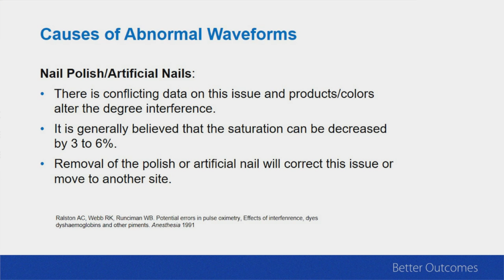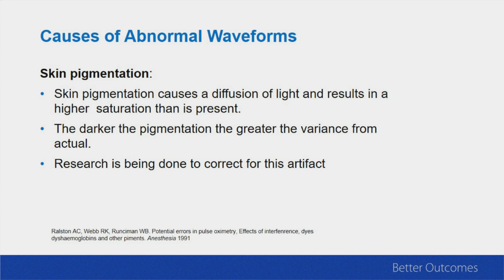And skin pigmentation causes abnormalities as well. This causes a diffusion of the light and results in a higher saturation than is actually present. So we may be hypoxic and we don't think they are. And the darker the pigmentation, the greater the variance from actual it can be. There is research being done to correct this, and it's a calibration issue, trying to calibrate the pulse ox sensors to the different skin pigmentations. But as it stands right now, we don't have any device that is giving us a correction factor for this.